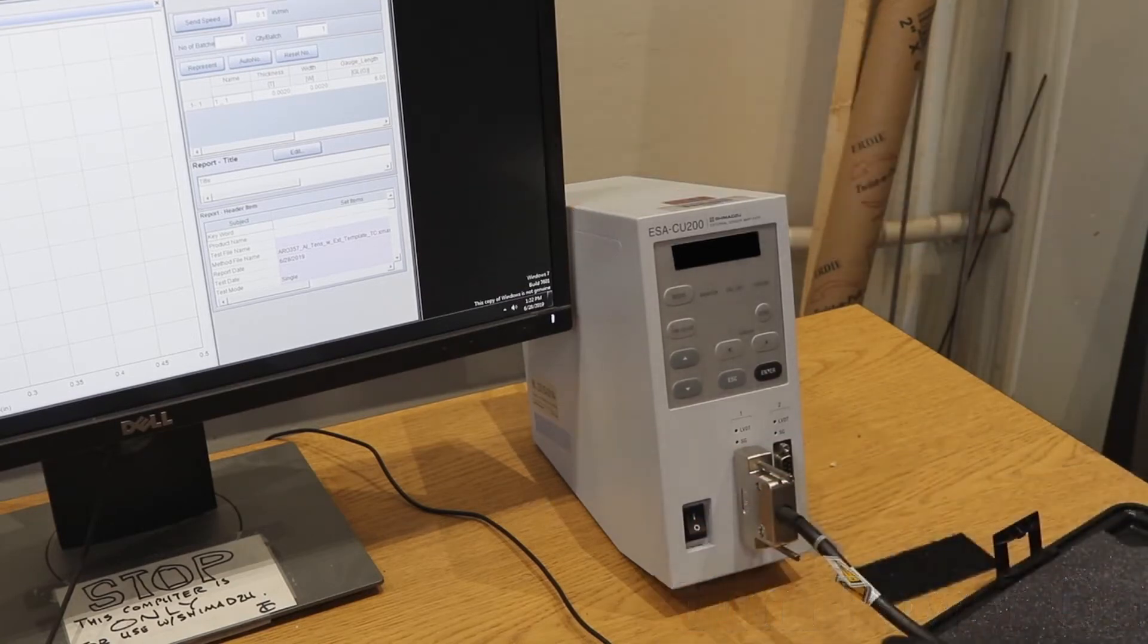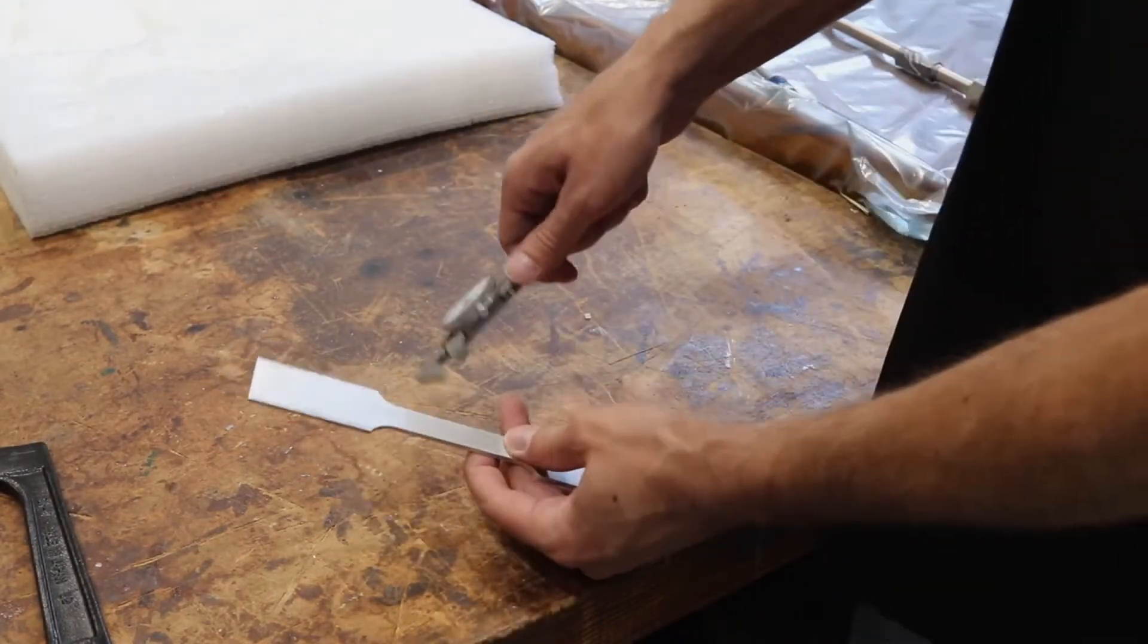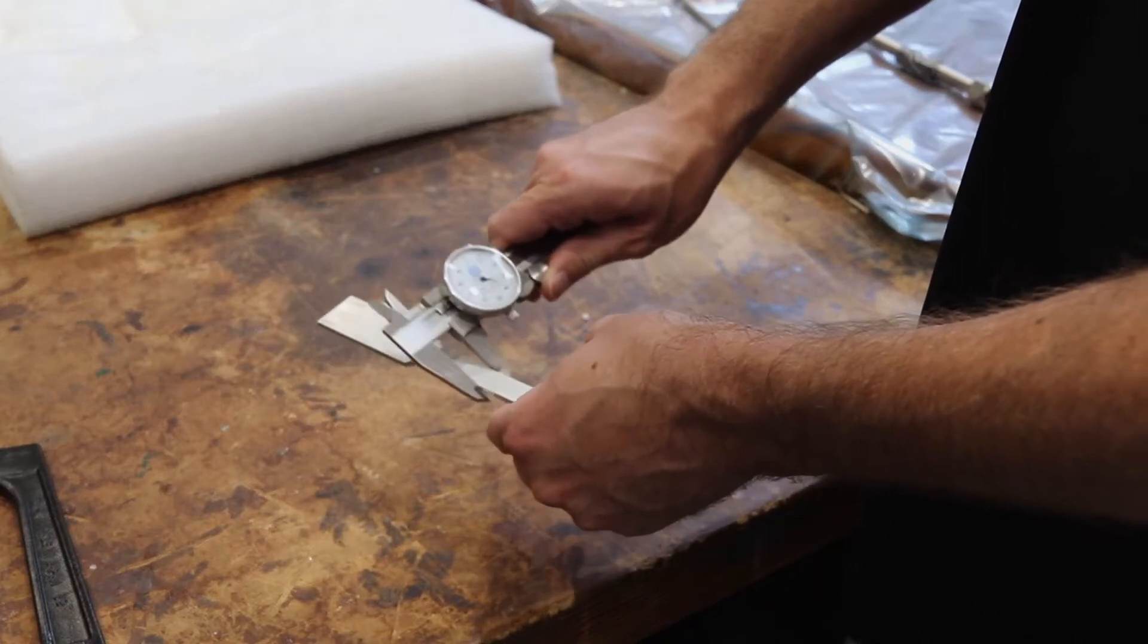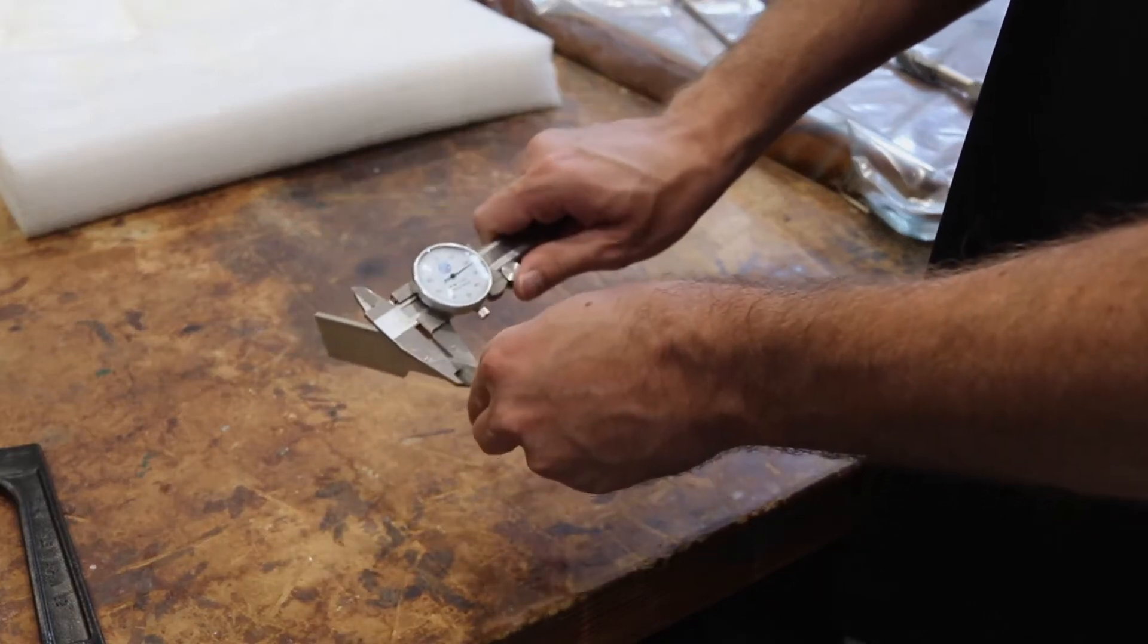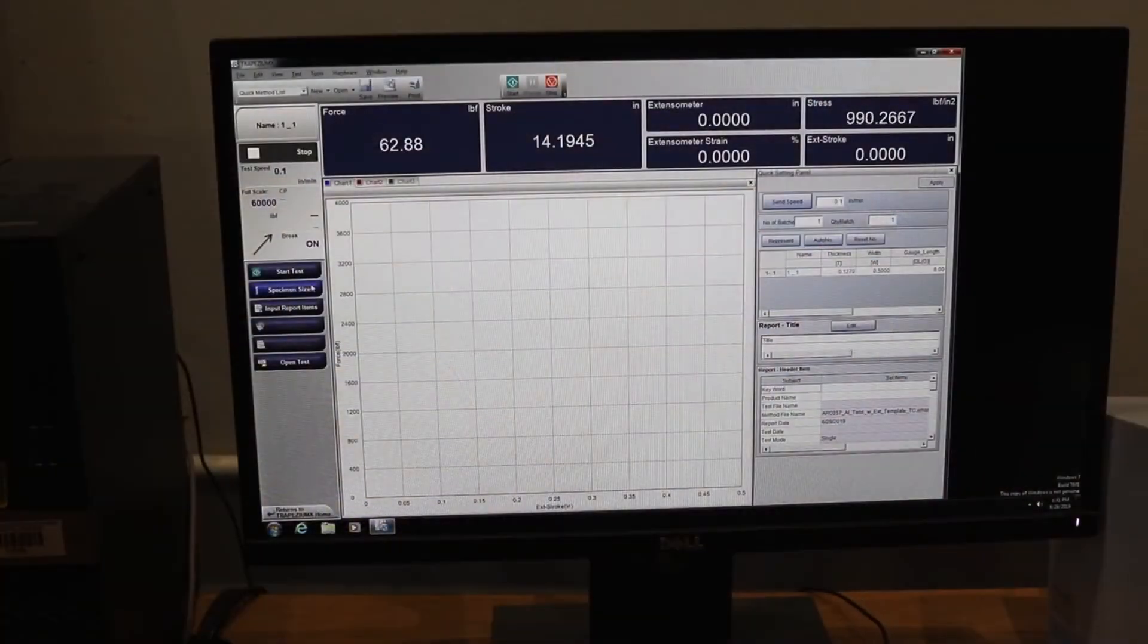Our next step involves measuring our specimen. The important measurements involved are the thickness and the width at the smallest section of the dog bone. If you are unfamiliar with using calipers, there is a video available. Now we will input our measurements obtained into the software.